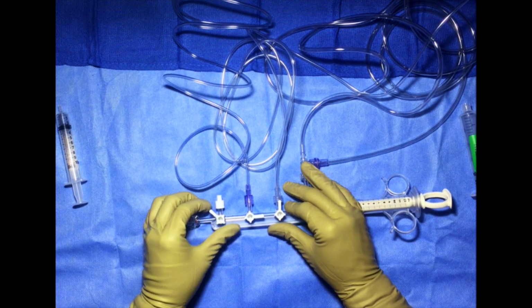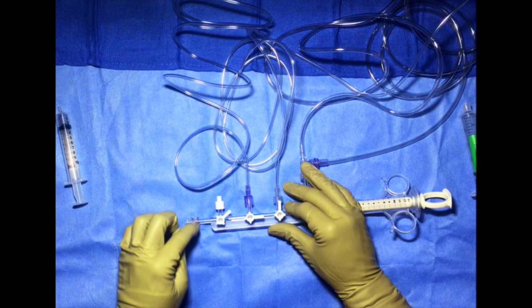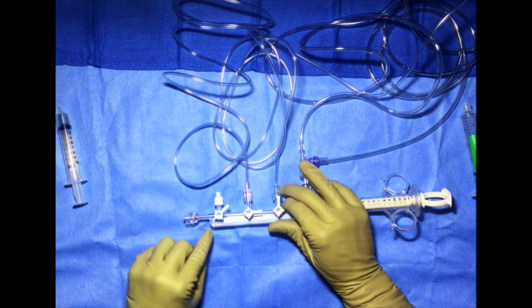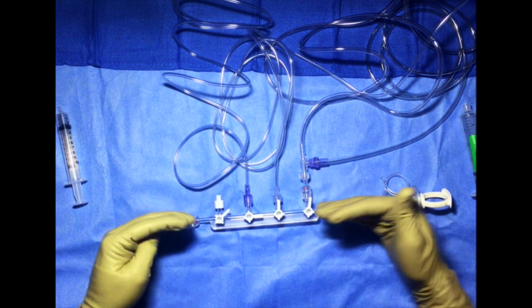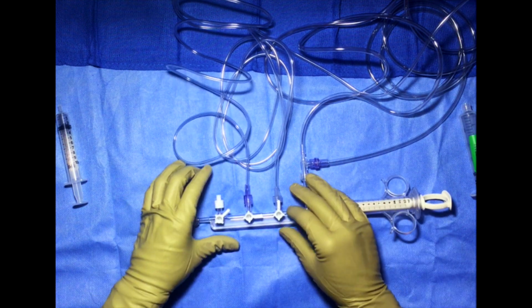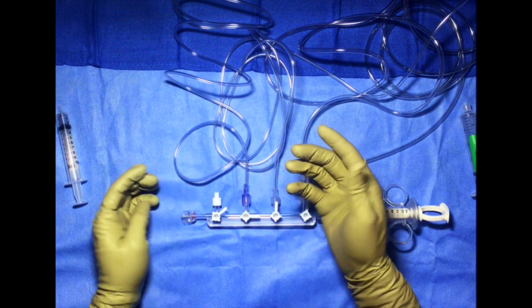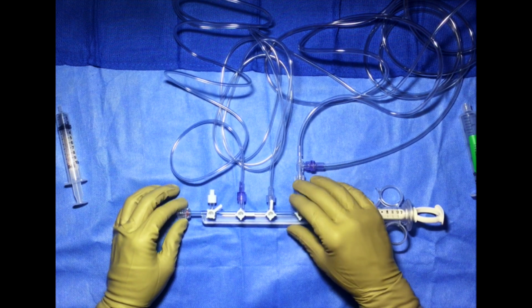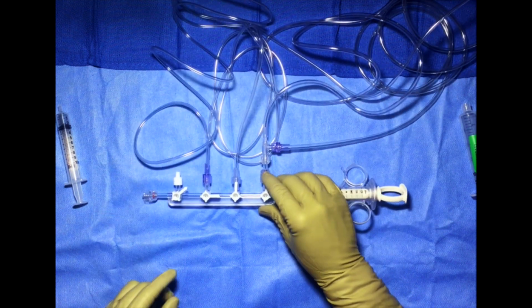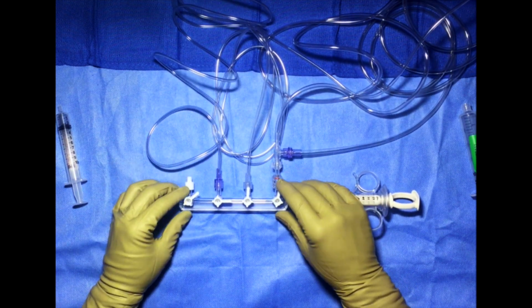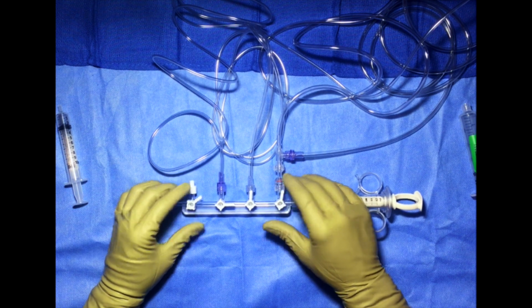If I turn it 45 either way, there are no holes that you can really expose at all. There's no way for anything to get to them, so that's why we zero it that way. No pressures could get in. So we zero it at the phlebostatic axis. If it's on the table, sometimes we call that table mount. I would just call that table top.